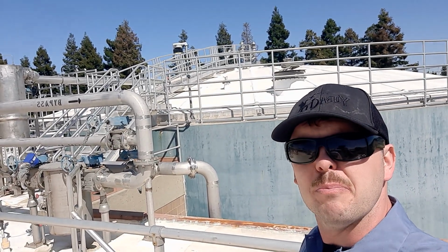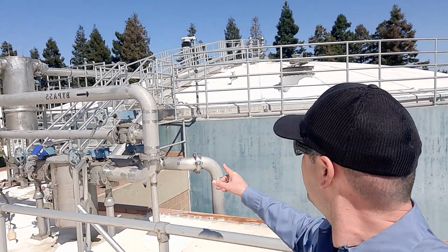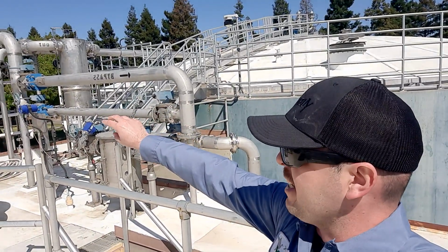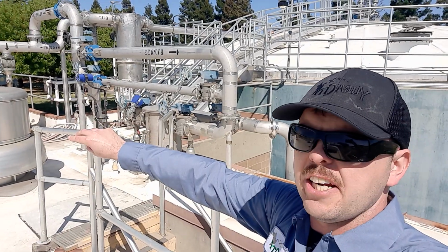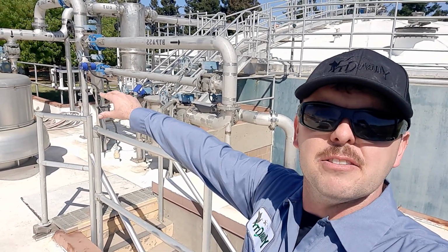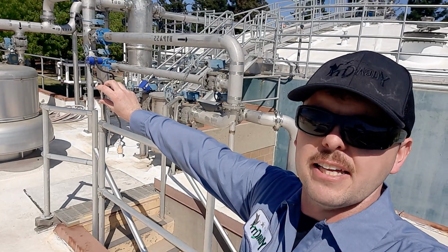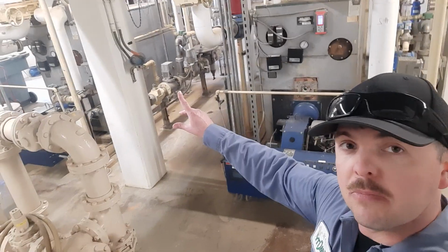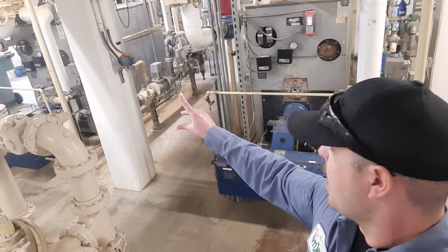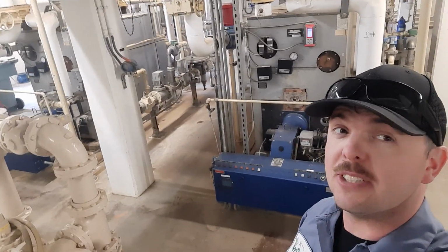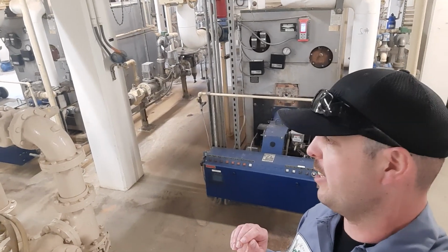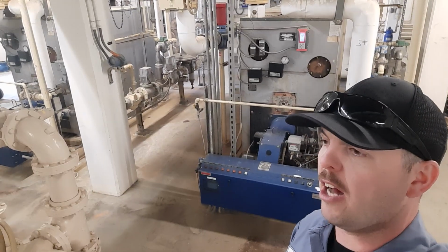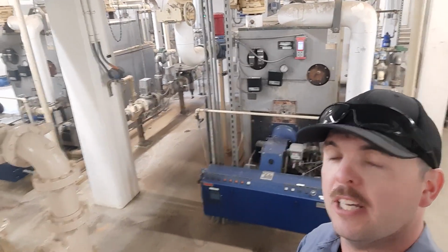Methane gas is a byproduct of treating wastewater, and it's collected from the top of these digesters through these pipes, where it's going to be compressed and pumped down into boilers that we're going to use to heat the sludge and help lessen the cost of our process. Here you can see our two different boilers. It's used to heat the sludge, and that makes sure that the bacteria growing in the sludge is at an optimum temperature to treat the sludge.